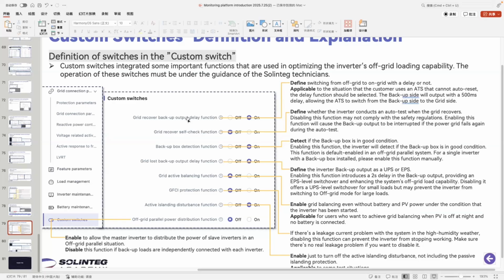But what if the grid has recovered? Our inverters have a very quick off-grid and on-grid switch time, so this process can be finished in less than 10 milliseconds, and some old version ATS won't be able to notice that, so it won't switch from the backup side to the grid side. If we turn on this function, we add a delay to the backup port output. For example, when the grid has recovered, it will stop the backup output for a few seconds, which is enough for the ATS to switch the power provider. In this case, the system can run normally.